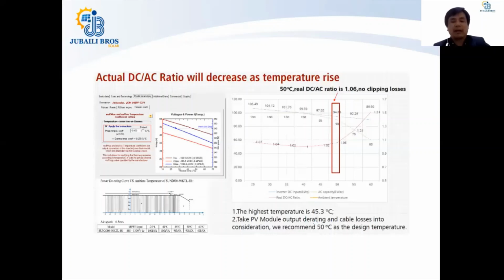The DC-AC ratio is a common discussion among designers: what sort of DC-AC ratio can we put? It actually depends on the environmental factors, the type of installation that you are doing, and the angle of your PV plants normally. But an ideal DC-AC ratio can be figured out based on the project, and a good DC-AC ratio is normally between 1.15 and 1.3. You can go up to 1.4 with Huawei inverters, and Huawei can provide you such inverters that you can use. If you want to go above a 1.4 DC-AC ratio, we recommend that you come back to us and we can get your project verified for high DC-AC ratios from Huawei.